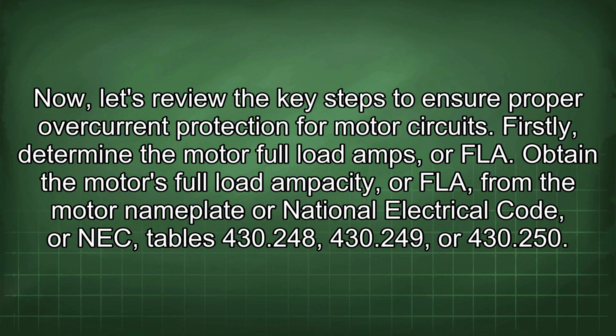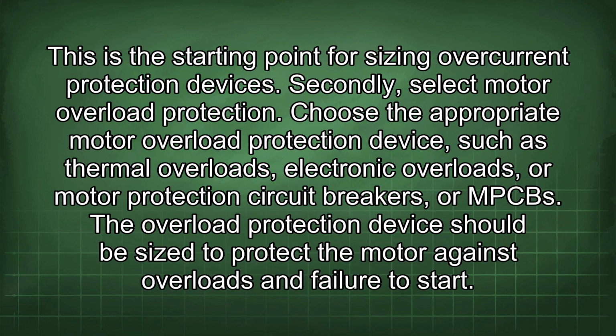Now, let's review the key steps to ensure proper overcurrent protection for motor circuits. Firstly, determine the motor full load amps, or FLA. Obtain the motor's full load ampacity from the motor nameplate or NEC tables 430.248, 430.249, or 430.250. This is the starting point for sizing overcurrent protection devices. Secondly, select motor overload protection. Choose the appropriate motor overload protection device, such as thermal overloads, electronic overloads, or motor protection circuit breakers, or MPCBs.